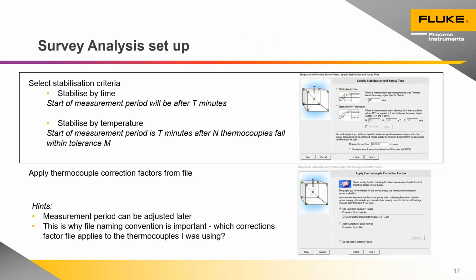So having set the tolerances, we then look at the stabilization criteria, one of the most important aspects of the TUS software. The software will automatically locate the stable periods that will be used for the survey. And here you can just select the method you prefer in finding that period. It could be that it starts simply a period of time after the thermocouples are in tolerance, or it could be that you want a subset of the thermocouples falling in tolerance, and you can even set a tighter tolerance on that should you want to start the period. And this is how the software will find those areas of stable readings at each of the temperature settings. It can be overridden later, and when we come to that, we'll talk about that again.